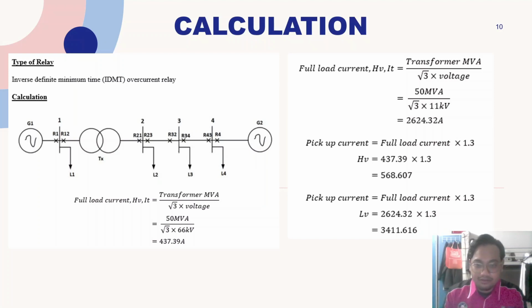Next, we need to find the pickup current, using the formula: full load current multiplied by 1.3. The answer for pickup current in HV is 568.607. Next, the pickup current for LV is 3411.616.